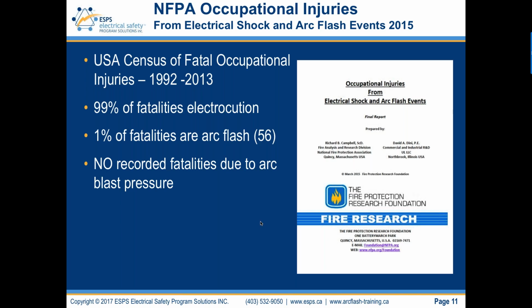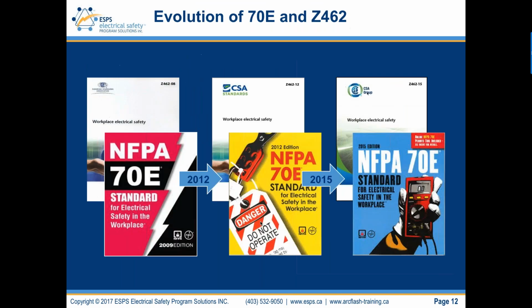As we move through this topic and talk about risk, it's risk-based language that we now need to use. Between the 2012 and the 2015 editions, the language changed 100% to risk-based language aligned with occupational health and safety management system standards. So everything we talk about with respect to arcing faults, arc flash, and shock should be risk-based. What's the risk level, low, medium, or high? What's the potential severity, or injury to damage to health, versus likelihood of occurrence? This is the risk language that the two documents now mandatorily require, and I'll talk about that a little more in the webinar.